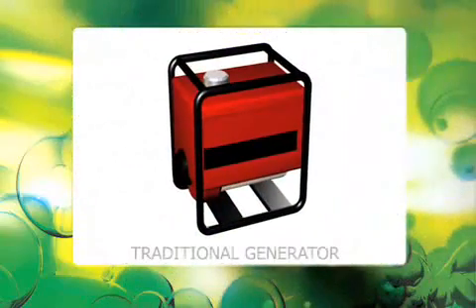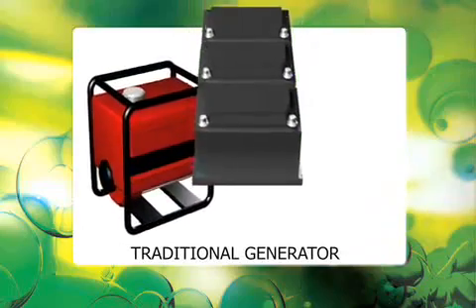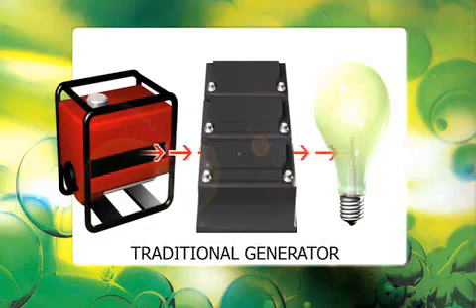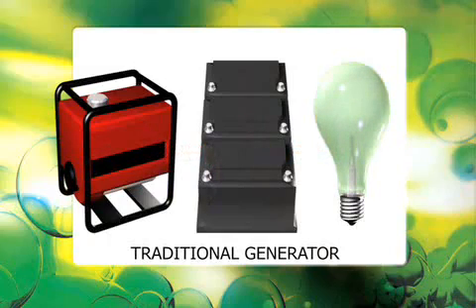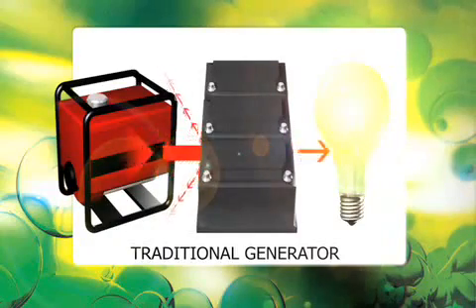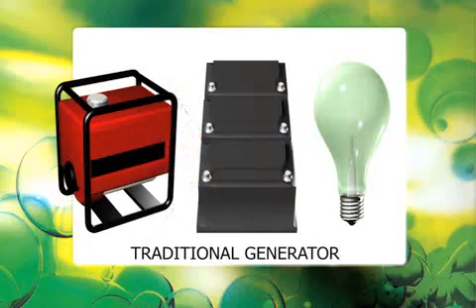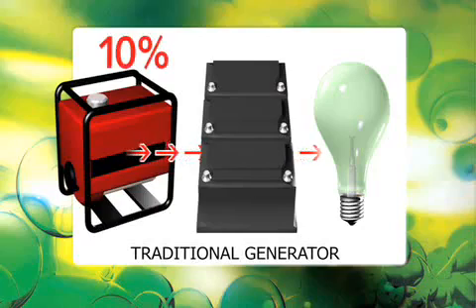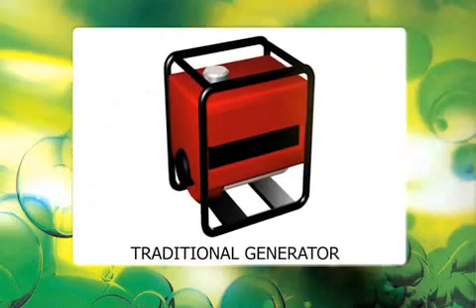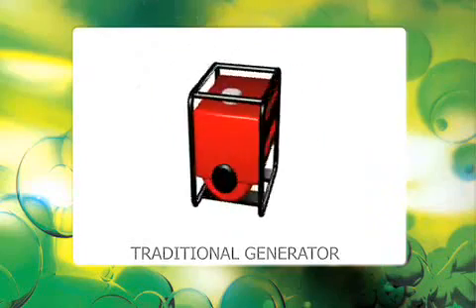Traditionally, generators have delivered most portable power needs. However, this technology is not an efficient way to charge and care for batteries. Battery bank sizes are specified to meet the application's base load, and battery technology benefits from a slow charging rate. In contrast, a traditional generator is usually specified to meet the application's peak load, which is achieved by running the generator at full power. Although it can reach around 20% efficiency when run at full load, a generator's efficiency falls dramatically, often to less than 10% when run at a battery kinder half load. Once we add other factors such as noise, vibration and emissions, there's a strong argument suggesting that a diesel generator is the wrong technology to charge batteries.